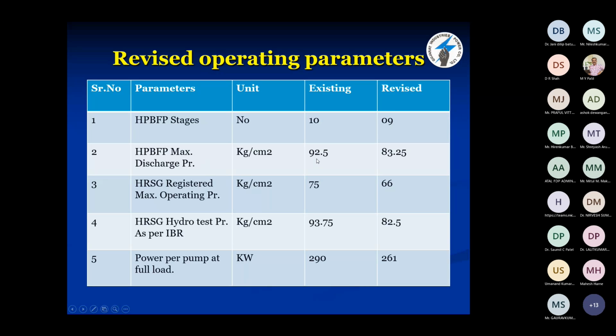Maximum discharge pressure was 92.5 kg. Now it is reduced to 83.25 kg. Now the HRSG was registered for maximum operating pressure of 75 kg. Then we approached the IBR authority, and we have revised our maximum operating pressure, and now the revised operating pressure is 66 kg.